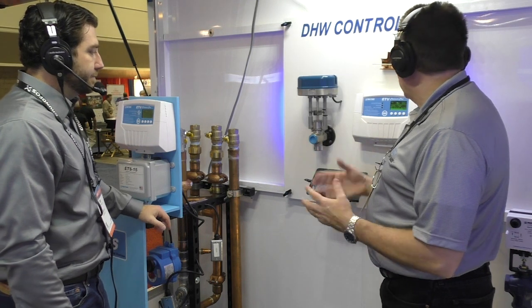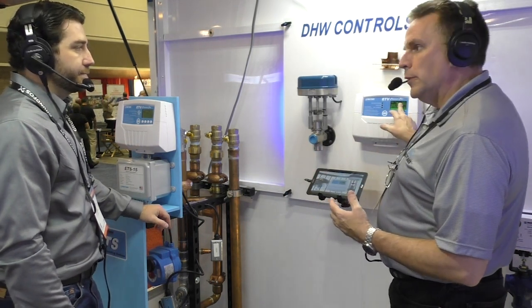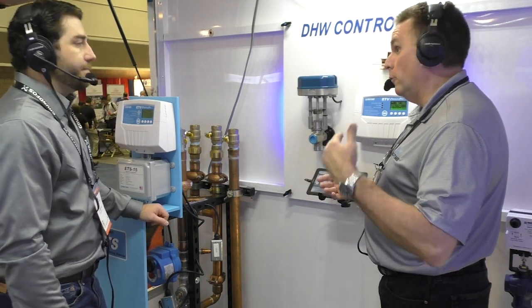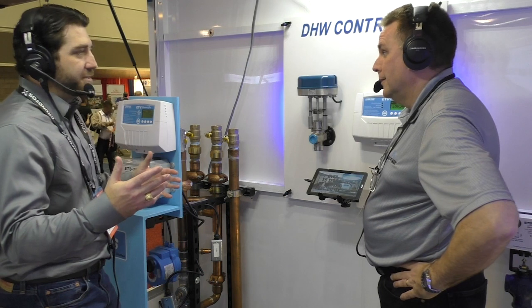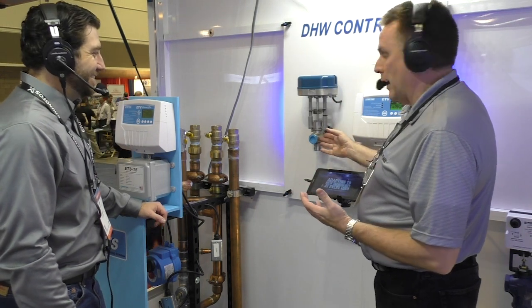So it's very quick to change out and get the customer back up and going. And the great thing about electronic is you can see what's happening, and the accuracy - plus or minus 2 degrees from half a GPM domestic flow all the way up to full flow. That's huge. In domestic hot water applications you have that big variable demand. I was just over at the Intelli-Hot booth, and we were talking about the same thing.